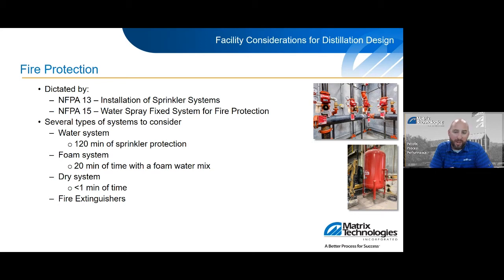Another system that can be used is a dry system. This would be a clean agent like FM200 or CO2. The advantage of this is it's a minimal duration of suppression required, and it's kind of a quick hitter. I've not seen it used too much in the spirits world. I've seen it mainly around isolation on equipment when you need to put that in an enclosed space. And finally, fire extinguishers. Just make sure that you've got those located in your facility. This can be laid out by your architect, your maintenance team, or even the company that supplies and services them for you. And another note on that too, just make sure that those are checked and serviced yearly.